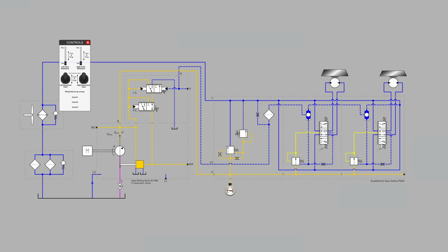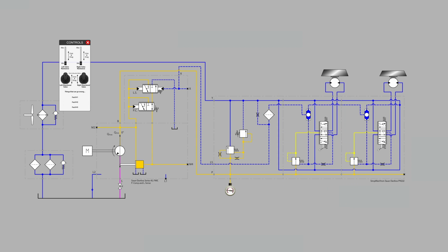And currently, our directional control valves are closed. You see that T-shape valve blockage on those two right-hand directional control valve symbols. So there really isn't any demand for flow. We're not asking for the motors to turn. So the pump moving between 0 and 2 degrees is just making up for internal leakages in the system and holding our pump outlet at port B on the pump symbol at our standby pressure, which will be a fairly low value, such as 300 PSI.